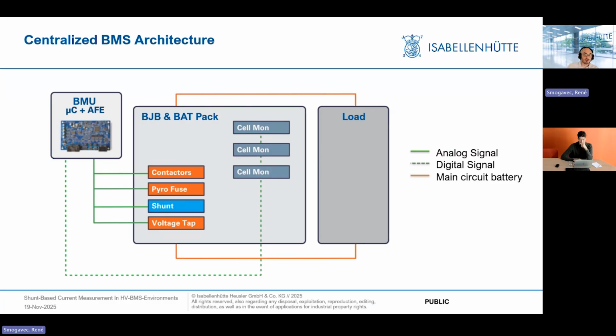Also, an important remark for these kinds of architectures is that HV batteries can fail for many reasons besides mechanical punctures. The service life of batteries is very dependent on electrical stress and how this is managed. And with the functionalities of the battery management unit, the BMU, the cell monitoring units, the CMU, and the battery junction box, the BJB, you really have to look out for safety. And with the shunt, with the right choice of it, you can look out for safety and get very accurate state of health and state of charge calculations.